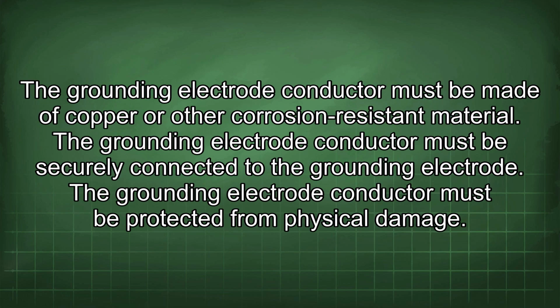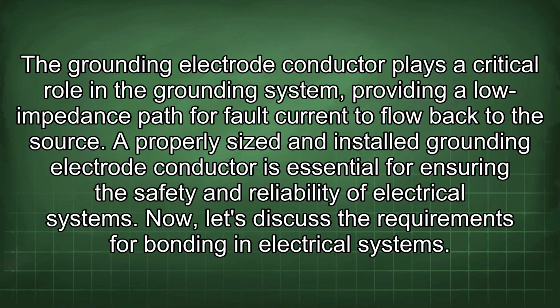The grounding electrode conductor must be made of copper or other corrosion-resistant material. It must be securely connected to the grounding electrode. It must be protected from physical damage. The grounding electrode conductor plays a critical role in the grounding system, providing a low impedance path for fault current to flow back to the source. A properly sized and installed grounding electrode conductor is essential for ensuring the safety and reliability of electrical systems.